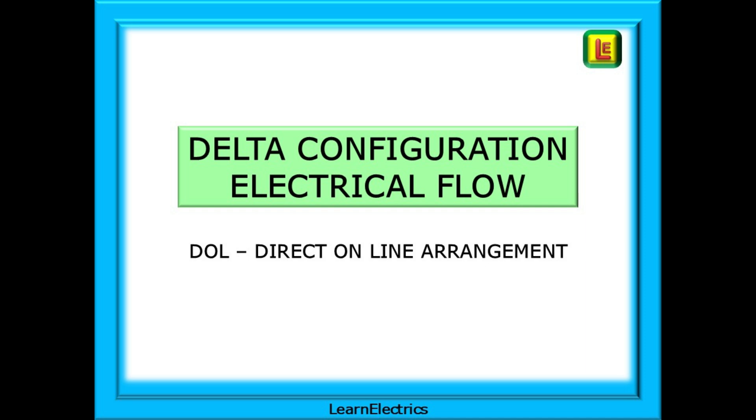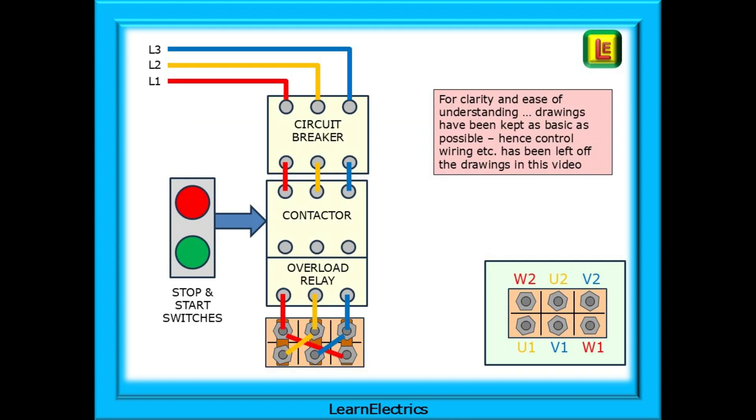Let's begin by looking at a direct on line motor in a delta configuration. For clarity and ease of understanding, the drawings have been kept as basic as possible. Hence control wiring has been left off the drawings in this video. The supply will enter the circuit from the distribution board at L1, L2, and L3. We have a three-phase circuit breaker, a contactor, and an overload relay before the power arrives at the motor block. There will be appropriate control wiring and a stop start switch box.